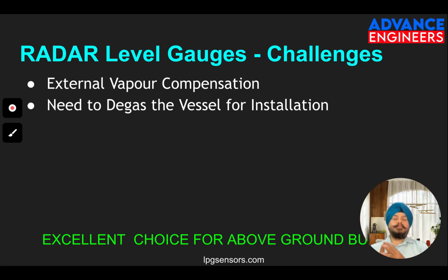Second, although radars are non-contact instruments, they need to be on the nozzle, and the nozzle has to be open so the waves can pass through. So if you have a nozzle with a blind, or just a basic gate valve, you simply cannot install the radar. You need a very clean path for the radar because the waves can only pass through cleanly, otherwise they won't be able to pass.